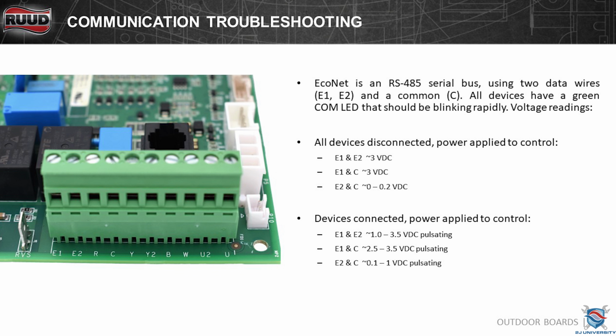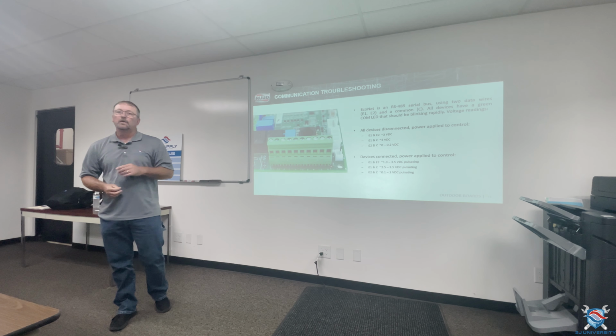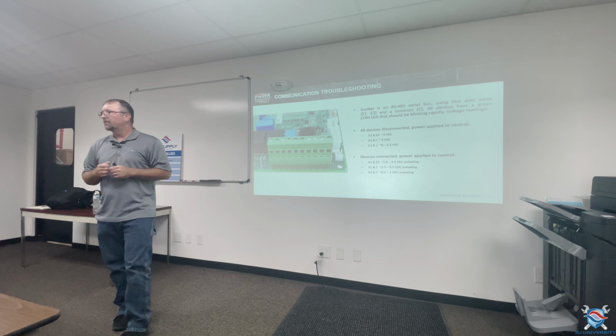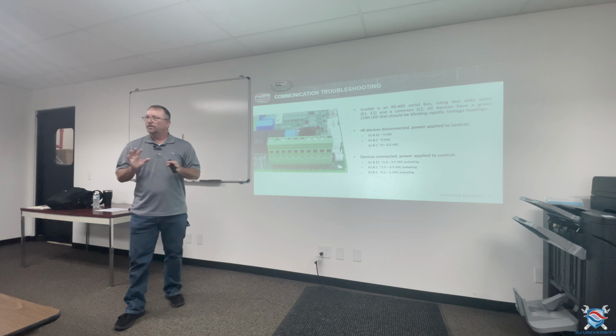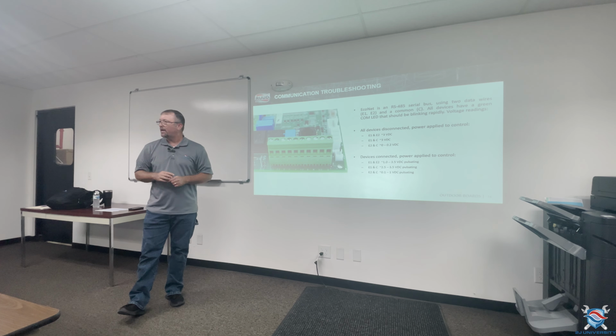So a little bit on troubleshooting on Econet. If you're using four-wire connectivity in the Econet application, on E1 to E2, you're going to read 3 volts DC. This can be checked at any given point within the system because that voltage is an output voltage everywhere it is connected. So if you're reading it at the outdoor unit, you can literally take E1 and E2 off the outdoor unit. You can read it there or on the wires, and you should have that 3 volts DC between E1 and E2. Between E1 and common is also going to be 3 volts. That's actually where you're getting that 3 volt signal. E2 is going to be 0 to 0.2 fluctuation. So if you're reading E2 to common, you should see 0.2 fluctuation. That's actually your full communicating back and forth.